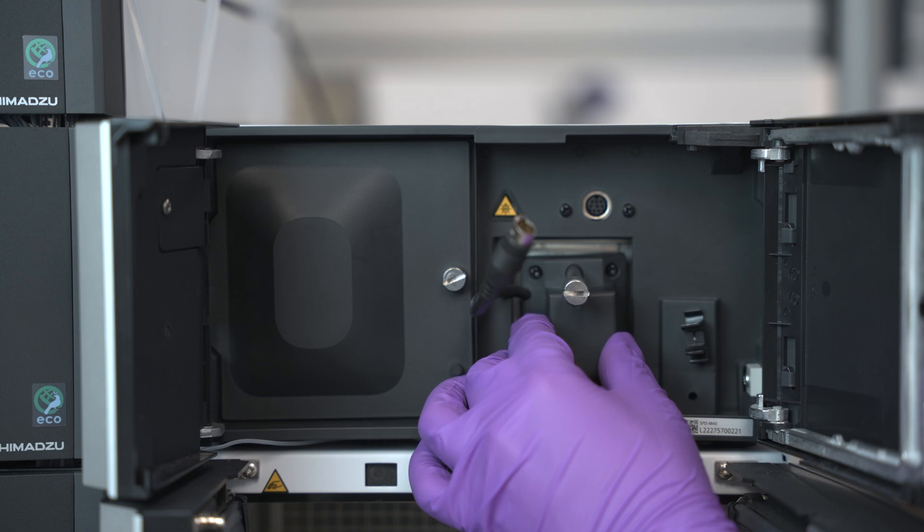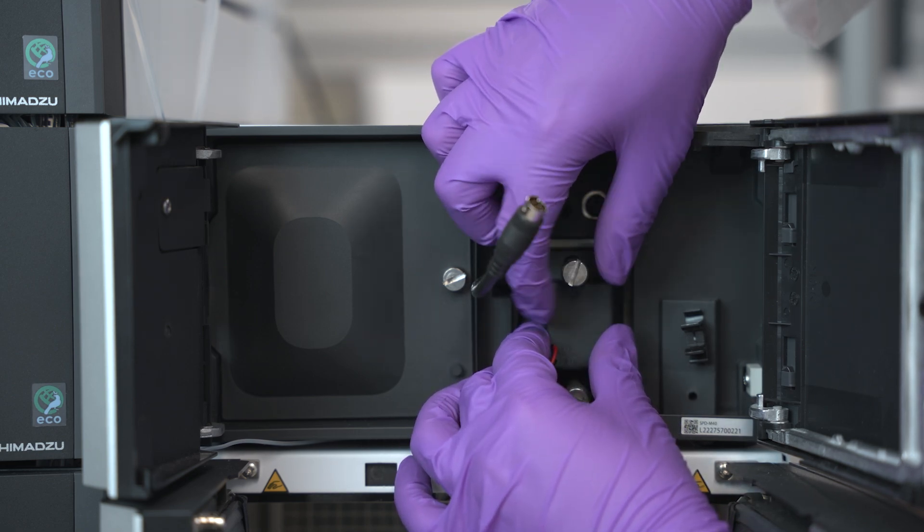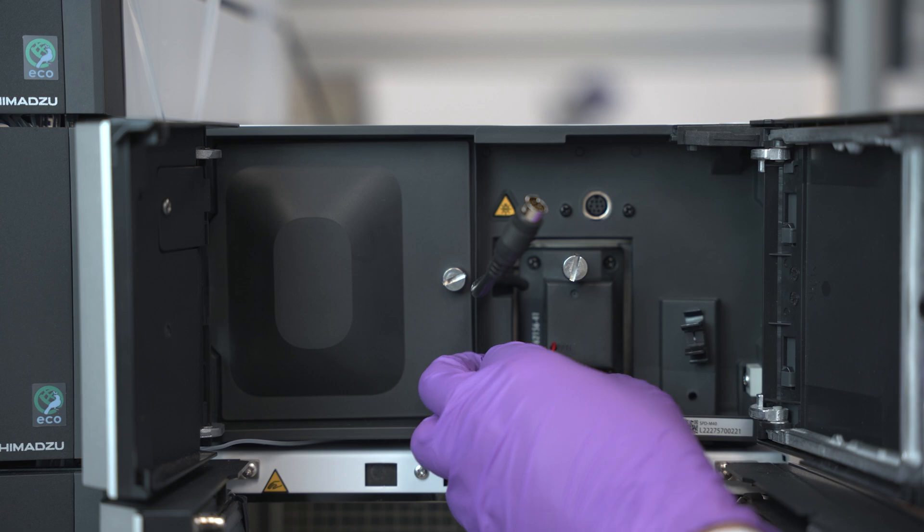Insert the flow cell into the detector. Hold the flow cell in place while you tighten the two cell mounting screws alternately.